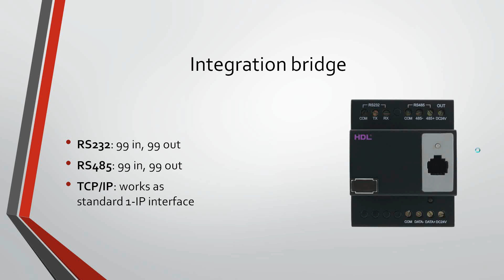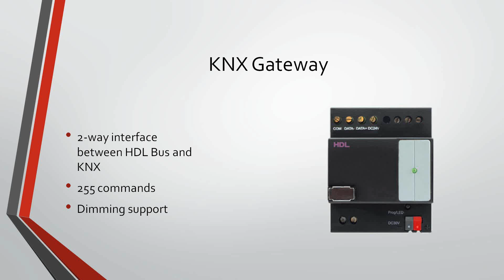There is also a KNX gateway. If you need to use KNX devices like Siemens, Gira, Berker, and others, or ABB, you can use it with the HDL Bus network. It supports up to 255 commands. It supports dimming, and it is fully two-way, so you get commands from KNX to HDL Bus and back.